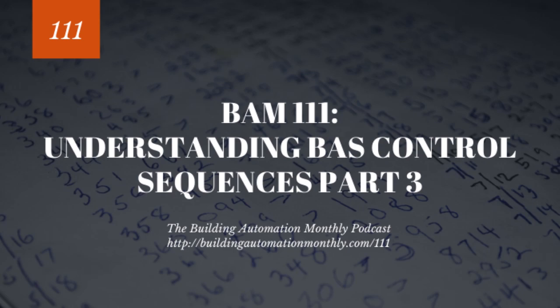VAVs are pretty cut and dry and pretty simple. Rooftops are pretty cut and dry and pretty simple. Air handlers, when you start to get into mixed air units that have what I call the trifecta damper setup, where you've got an outdoor air damper, a return damper, and an exhaust air damper, that is a little difficult if it is an exhaust air damper that can act independent of the outdoor air and return air dampers.